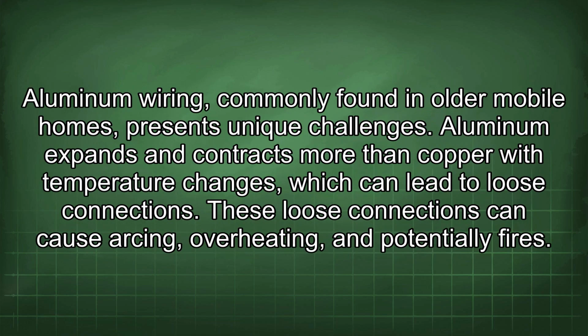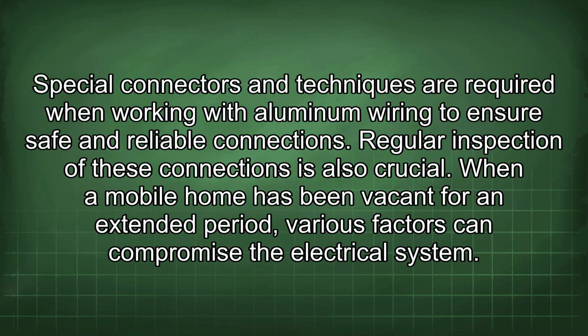Aluminum wiring, commonly found in older mobile homes, presents unique challenges. Aluminum expands and contracts more than copper with temperature changes, which can lead to loose connections. These loose connections can cause arcing, overheating, and potentially fires. Special connectors and techniques are required when working with aluminum wiring to ensure safe and reliable connections. Regular inspection of these connections is also crucial.